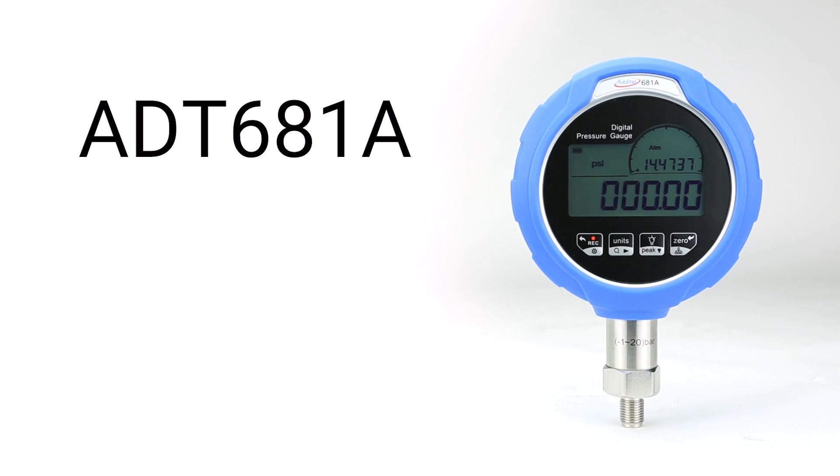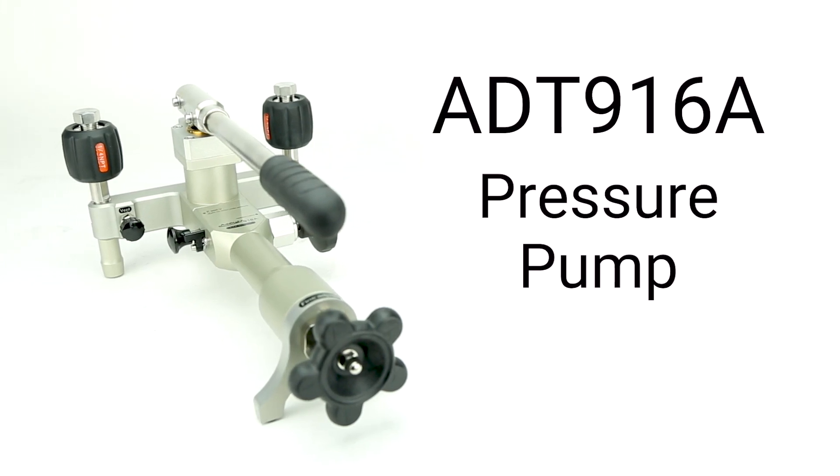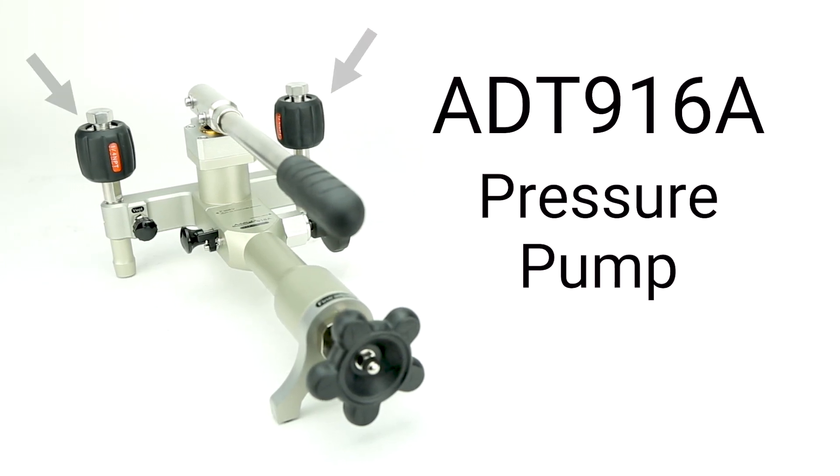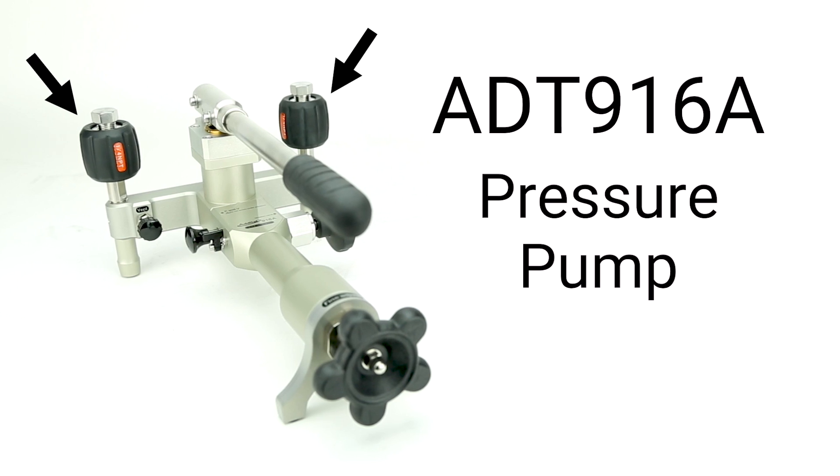For this, we'll use an Additel 681A digital pressure gauge, which easily exceeds this requirement. Finally, we need a way to generate pressure. An Additel 916A test pump will be used, since it has ports for both gauges built in to easily compare readings between them.